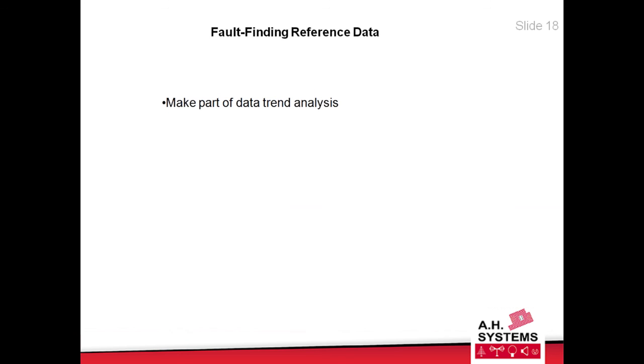When you've got one of these older systems, imagine your mind's eye some 10 year old, probably older, EMC test setup that probably needs quite a lot of replacement. A lot of the equipment's at the end of its useful life. Have data ready on hand should any of these parts of the test system fail, so you can very quickly get back online because you have data already held on file. You can make tests and compare with that data as a fault finding process.